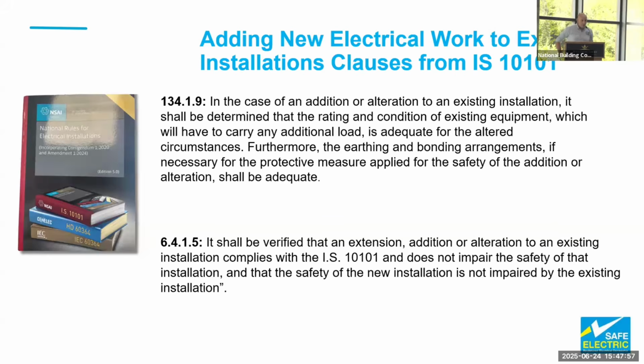So just what Neale mentioned there about the EV car chargers, making sure that an old existing installation that was done back in the 90s, what we would refer to as the meter tails, ensuring that cable can take this additional load. Furthermore, the earthing and bonding arrangements, if necessary for the protective measures applied for the safety of the addition or alteration, shall be adequate. So that's referring to earthing and bonding, and making sure the existing installation is the adequate size for adding on these extra loads.